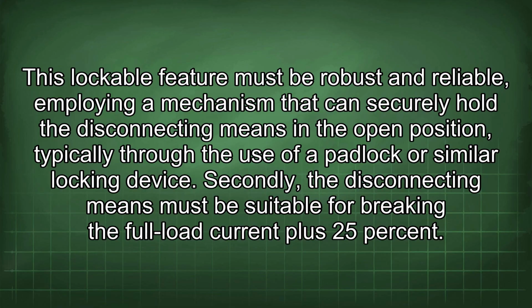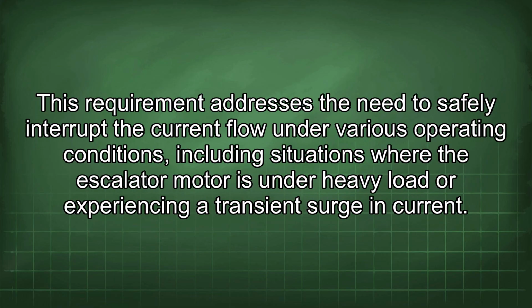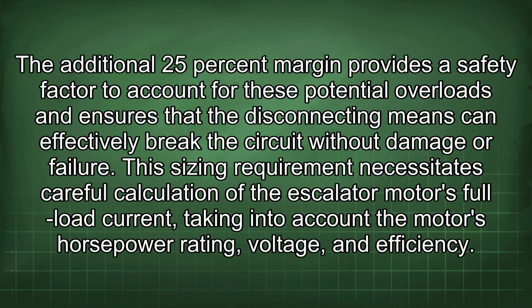Secondly, the disconnecting means must be suitable for breaking the full load current plus 25%. This requirement addresses the need to safely interrupt the current flow under various operating conditions, including situations where the escalator motor is under heavy load or experiencing a transient surge in current. The additional 25% margin provides a safety factor to account for these potential overloads and ensures that the disconnecting means can effectively break the circuit without damage or failure.